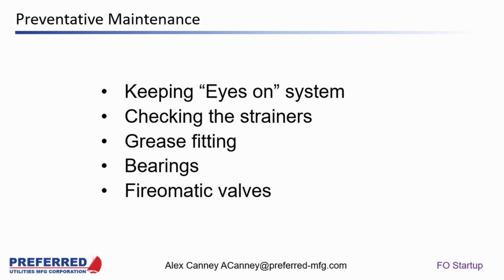Most of your pumps nowadays are sealed, so there's no need to do any greasing or anything of them. Same thing with motors. Most of the motors are sealed bearings, so you don't have to do that. But laying eyes on it to verify that everything seems to be rotating properly and that there's no leaks or anything. Verifying that any type of emergency valves, like a Fireomatic valve that is designed to shut off the oil coming from the tank in case of a fire, is taut and open and ready for service. That's just some of the things that could be done in like a quarterly or a semi-annual type test, or monthly even. Absolutely.